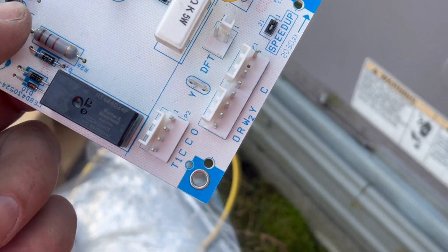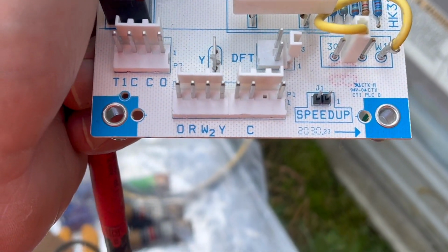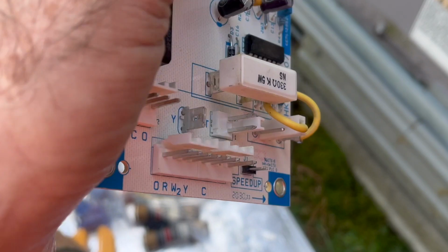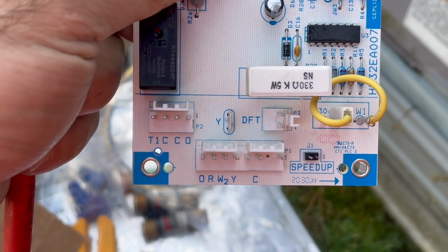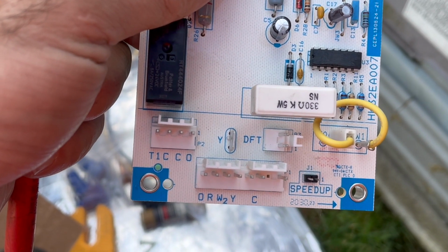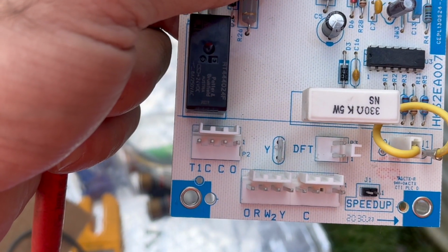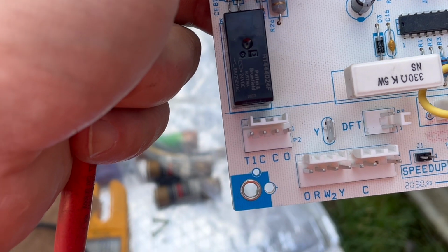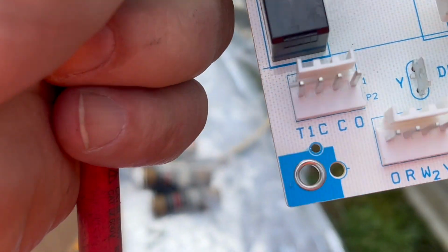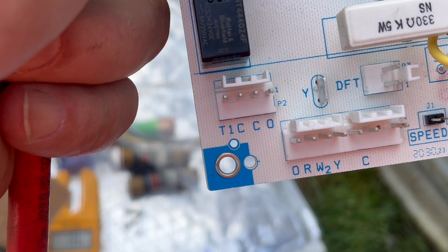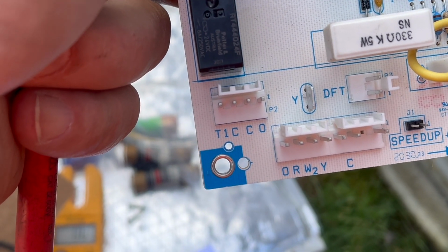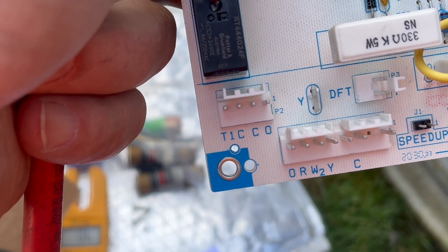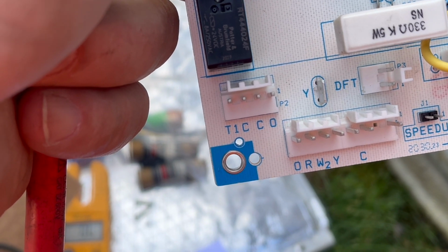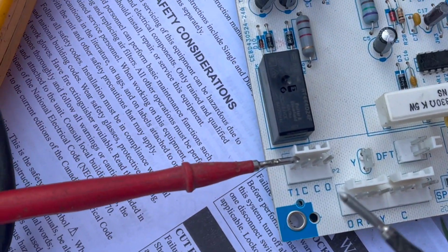Okay, Y is basically the Y on that long terminal there, just hooked to that little spade connector that says Y on the back, so it's just basically a junction block. The Y goes out on that blue wire, plugs on that, and winds up coming back over here on T1 on this smaller plug. So T1 to ground is what I was testing, basically checking if all the pressure or loss of charge switches were closed. So I've got the one stuck on T1 there.